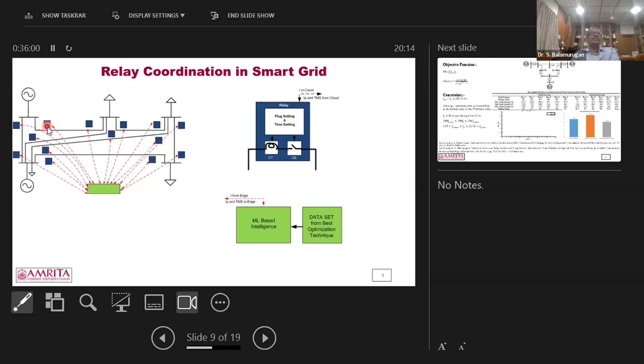So considering this constraint and this objective function, we were able to achieve the time setting and the current setting of each relay in the network. Once that is decided, the cloud will automatically transfer the TMS value and the IP value to this edge, and the edge is ready to function. Whenever the network changes, the time setting and the plug setting will automatically get updated, and it will be ready to protect and also ready to do the coordination.